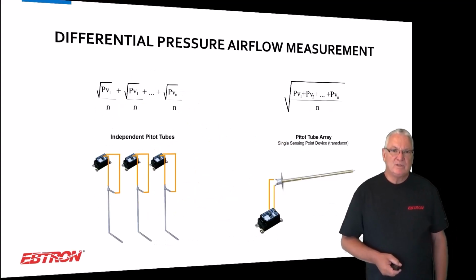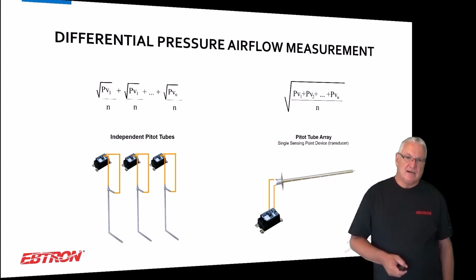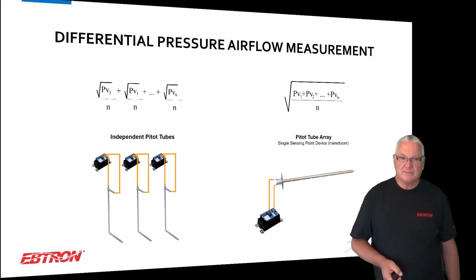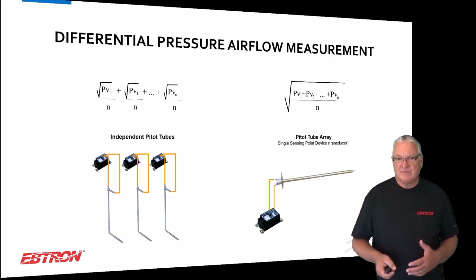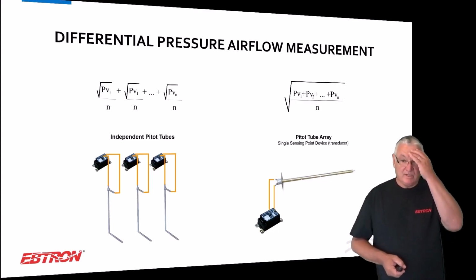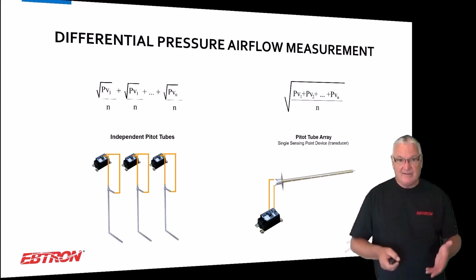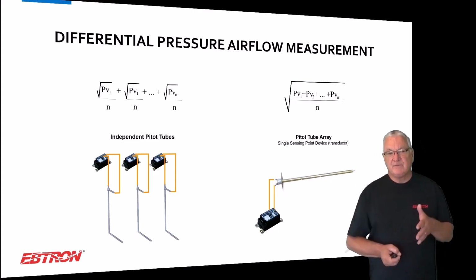The other problem with DP is you're only using one sensor. So you have a non-linear response to flow for each one of these points, and you're basically averaging them, and it's just simple basic math. If I put pitot tubes up here, if I have 3 pitot tubes, like an air balancer uses, and I measure 3 points, I have to take the square root of the velocity pressure at each one of those points before I calculate the flow, and that's essentially what that equation on the top left there is.